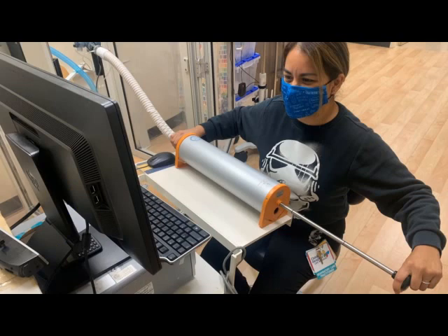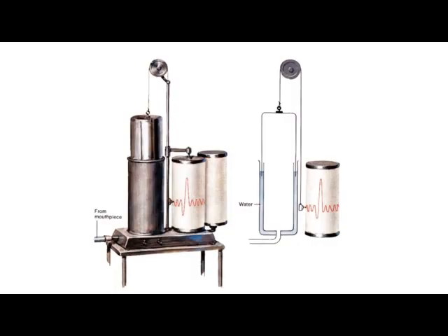If we put 3 liters in here, this pneumotach is going to measure flow. The computer will integrate that, and so it should also read 3 liters. That's really the way that flow is calibrated, and generally in pulmonary function systems, this is done daily.